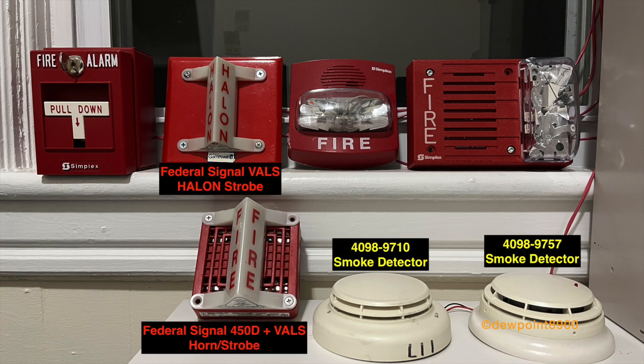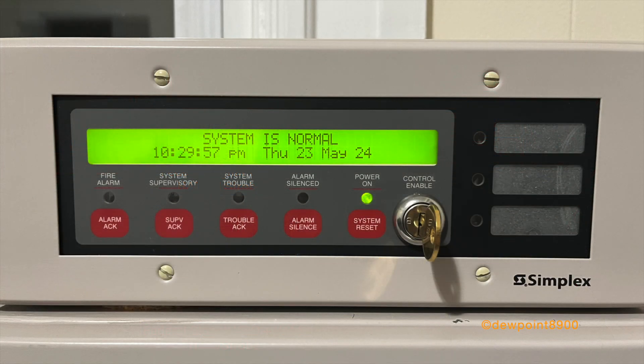On the agent release side, we have a 4098-9710 smoke detector and a 4098-9757 smoke detector. The signals include a Federal Signal 450D horn with a VALS strobe, and a Federal Signal VALS halon strobe. In addition to the panel, there's also a 4606-9101 LCD annunciator on the system.